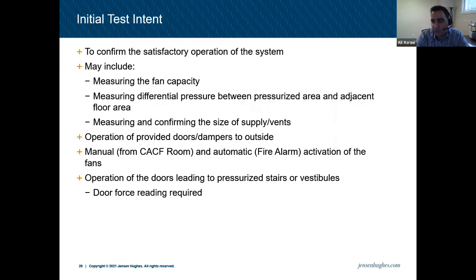Sometimes measuring and confirming the size of the supply and vents, and operation of the doors and dampers. Is anything discharging to outside, like a door discharging to outside, or is it a damper? Is it opening properly and whatnot? Manual activation from the CACF room and automatic activation of the fans by the fire alarm system. We have to confirm that. And operation of the doors leading to pressurized stairs or vestibules. We're going to talk about door force readings, which are required. We have to do that.